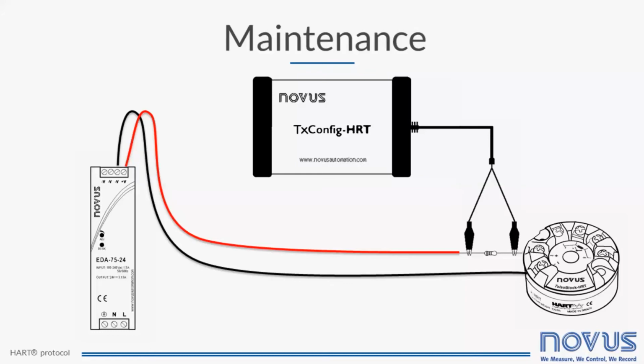For the configuration and maintenance of a HART device, you only need a device that reads the HART protocol. It can be a modem or a handheld. This equipment has the ability to read any HART device, regardless of manufacturer. There is no need to carry various types of maintenance tools, either a resistor that the field technician can carry with the modem, or it may already be installed directly on the HART device, just awaiting the modem connection.